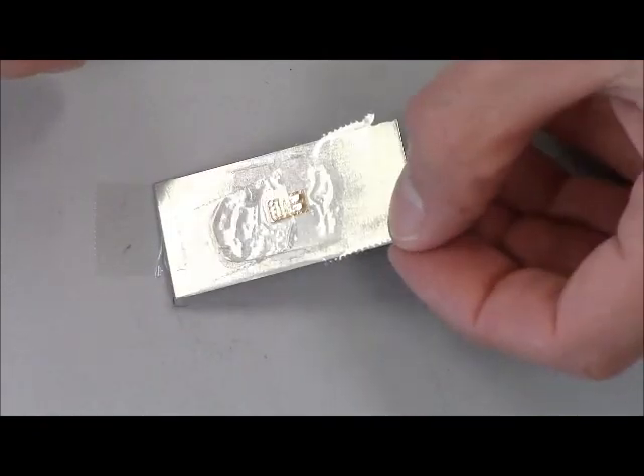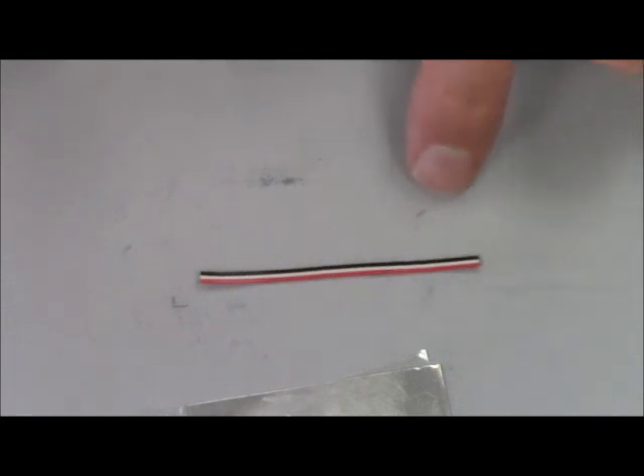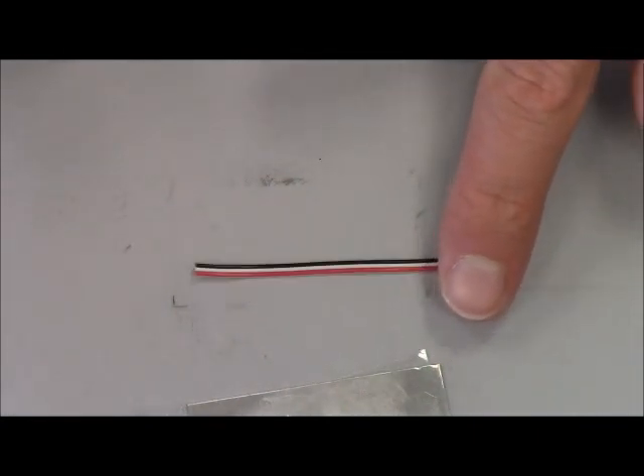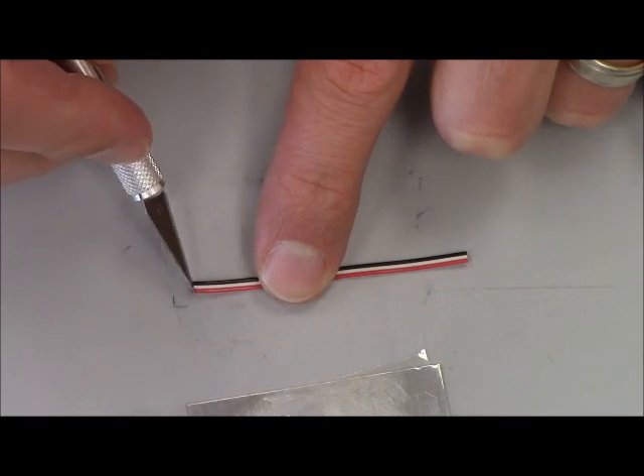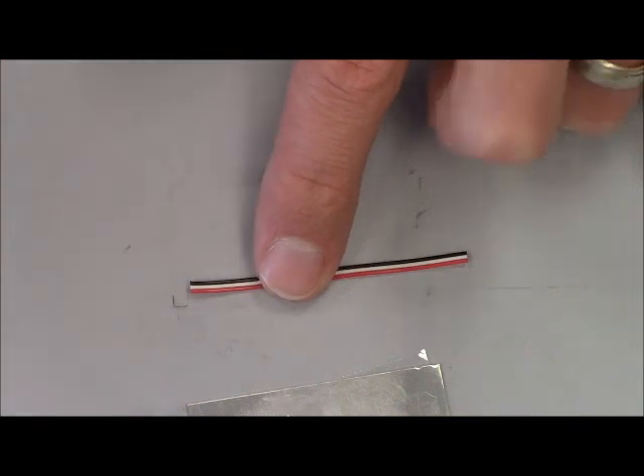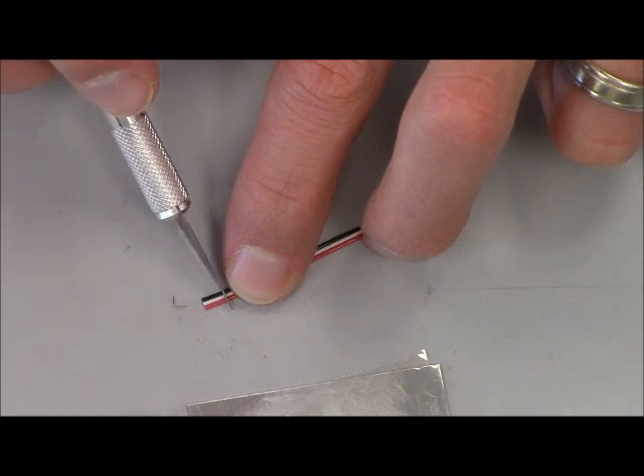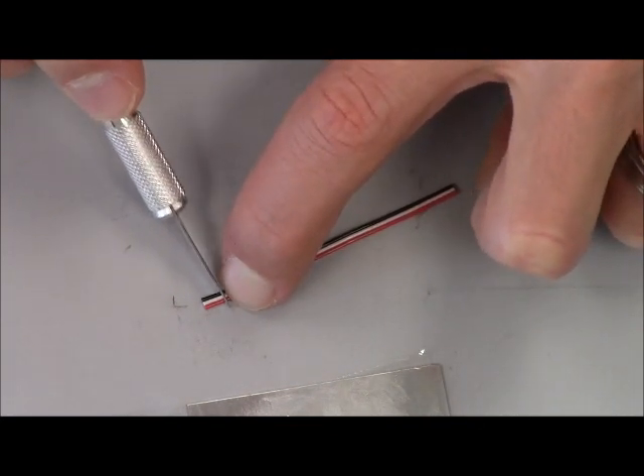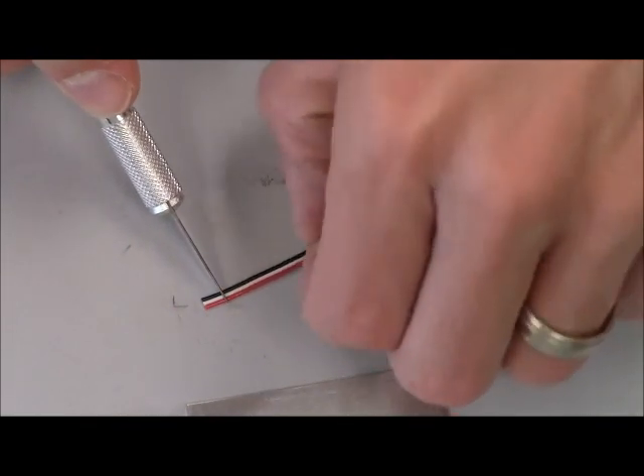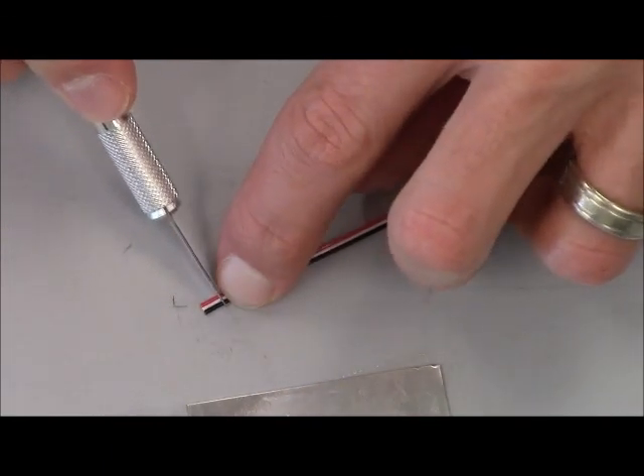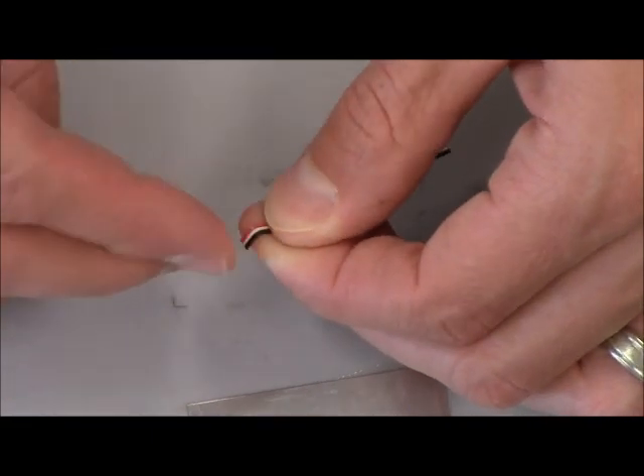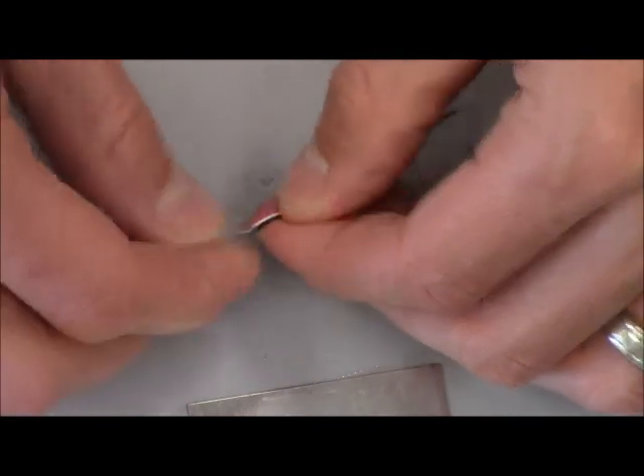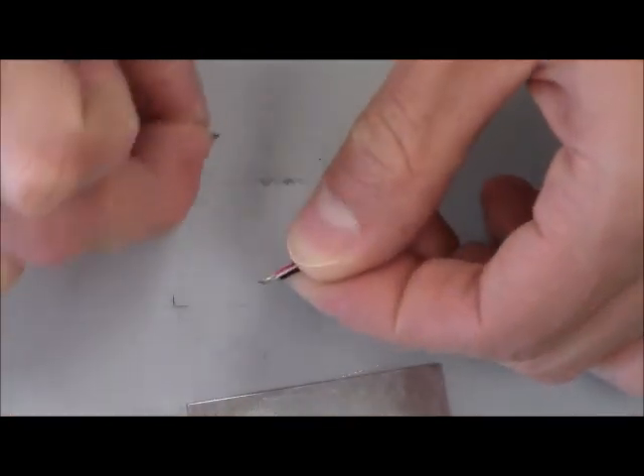I'm going to start off by taking a short piece of wire. Taking a short piece of wire on one end, that would be the end that would be connecting to our strain indicator. Obviously, we would need a longer piece of wire, but right now we're just practicing soldering. The other end, though, we do need to strip back a small amount so that we can solder to our strain gauge. As far as stripping goes, I just take an exacto knife and back off about an eighth to a quarter inch, and I score the wire itself, the insulation I'm sorry, and then flip it over and try to do the same in the same spot. Again, trying not to go into the conductor inside. At this point, I'll fold it back and forth to try to open up that score. And once I do that, I can usually take my fingernails and pull the insulation off.